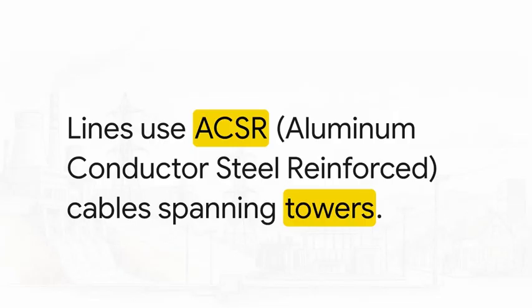So what exactly is all this power physically traveling on? Well, those massive metal towers you see along the highway are holding up overhead transmission lines. And these aren't just solid copper wires hanging up there. They typically use what's called ACSR, aluminum conductor steel reinforced cables. It's a brilliant engineering compromise. The aluminum is conductive and lightweight, letting the electricity flow easily, while the steel core running down the middle provides the immense tensile strength needed to support those crazy long spans between towers, so the heavy wires don't sag dangerously close to the ground on a hot day.